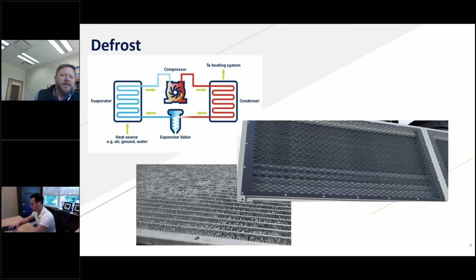Depending on how much ice there is, that's going to dictate how long we stay in defrost. And of course, depending on the manufacturer, you're going to have different methodologies of defrost, but across the board, everyone that utilizes an air source heat pump is going to have to manage that.